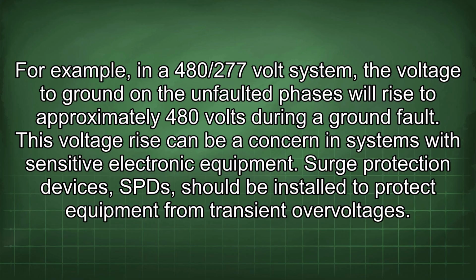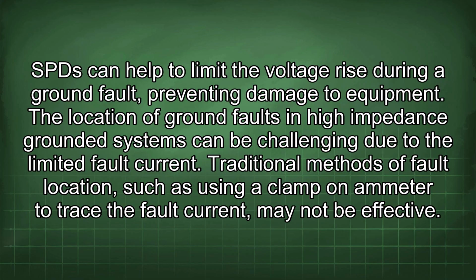Surge protection devices, SPDs, should be installed to protect equipment from transient overvoltages. SPDs can help to limit the voltage rise during a ground fault, preventing damage to equipment.